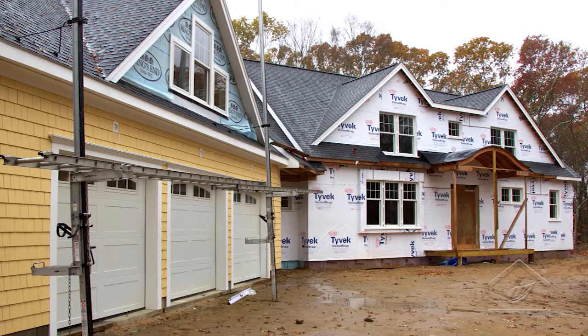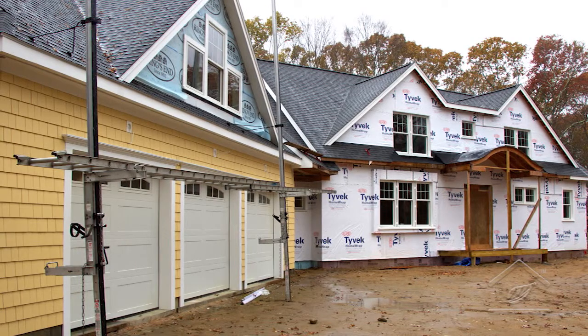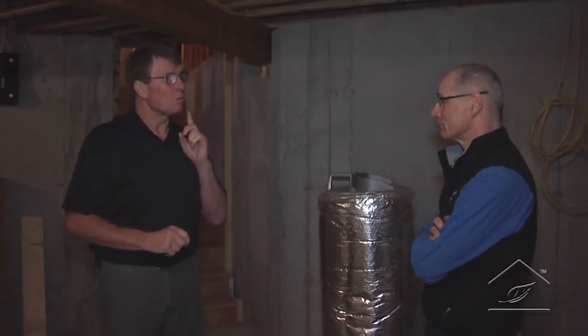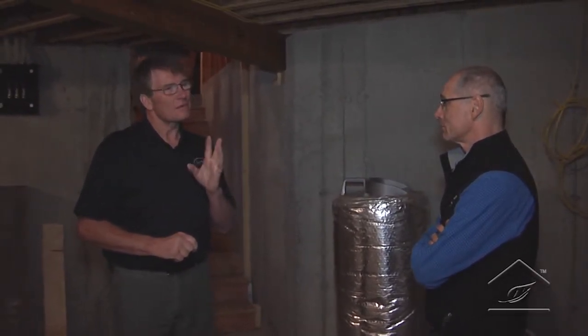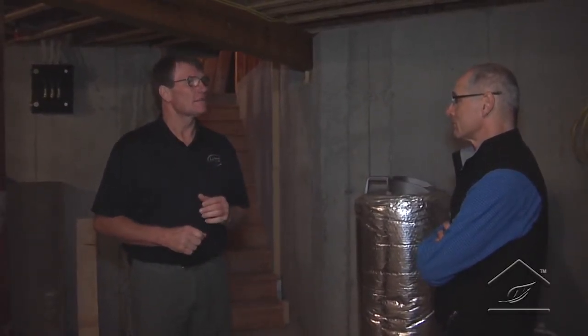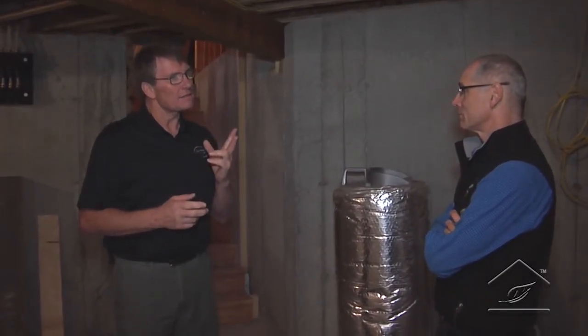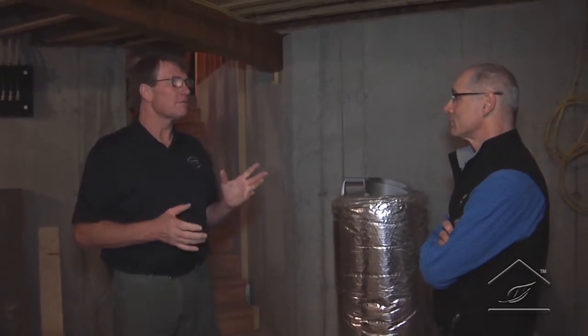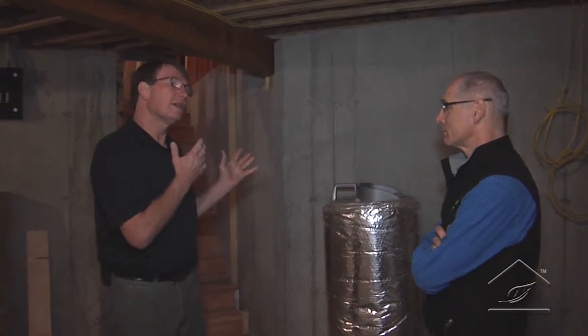Dave, I need a few more particulars to be able to produce a layout or a design. And we have turnkey kits that are available. We've talked about how you can have electric backup or gas backup. We need one tank. A couple of sizes are most popular, 80 gallon or 119 or 120 gallon, which are the best choices for the size you're looking at. And then 2 to 3 panels is a good target, and you've got plenty of room on the roof to choose what you might want, particularly in the size that you wish.